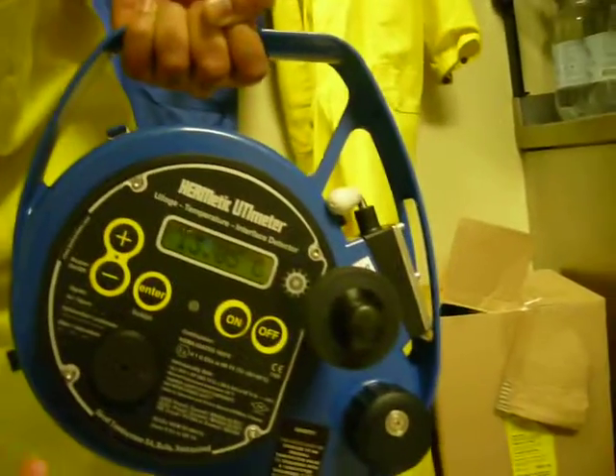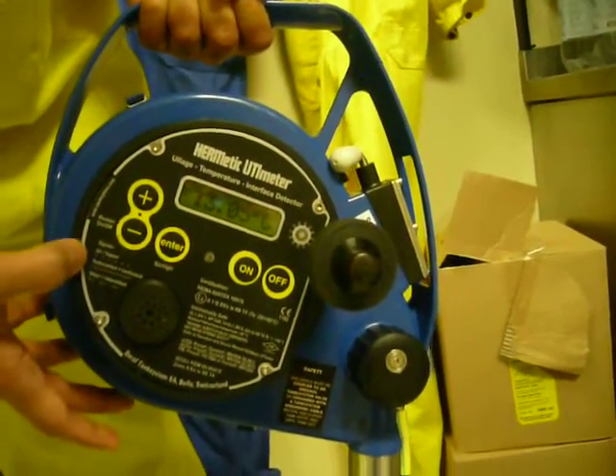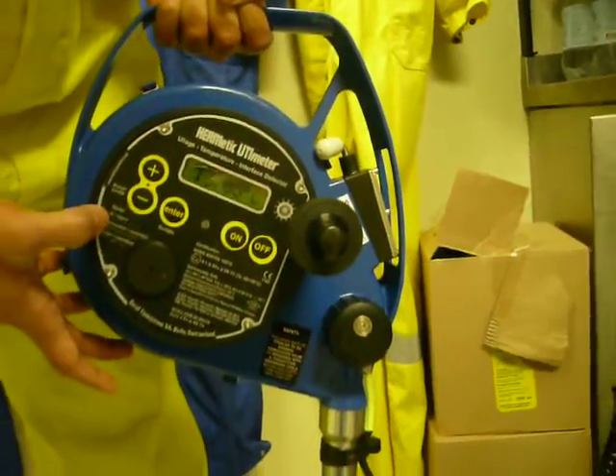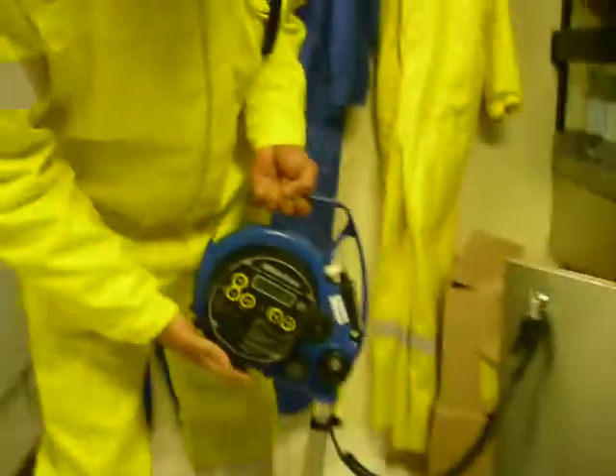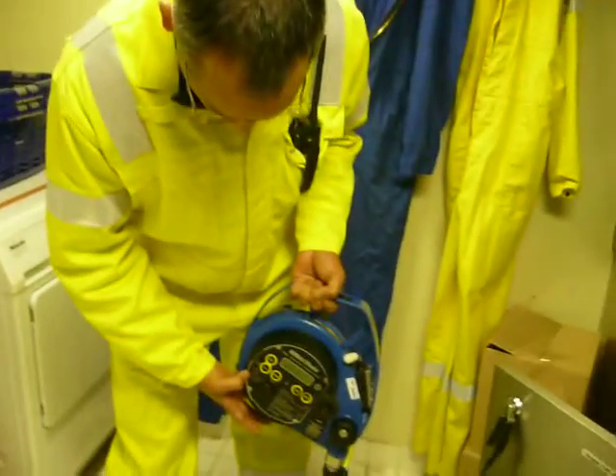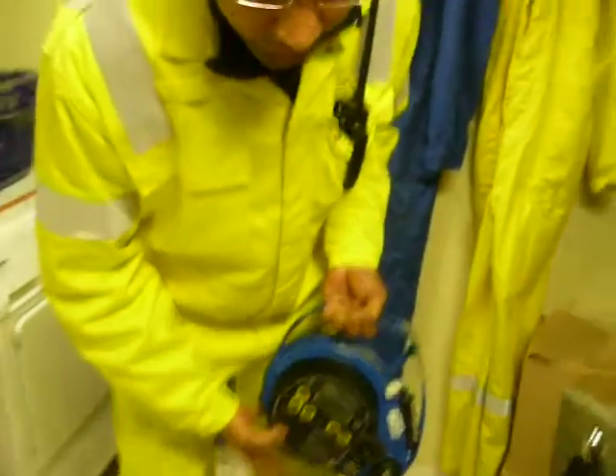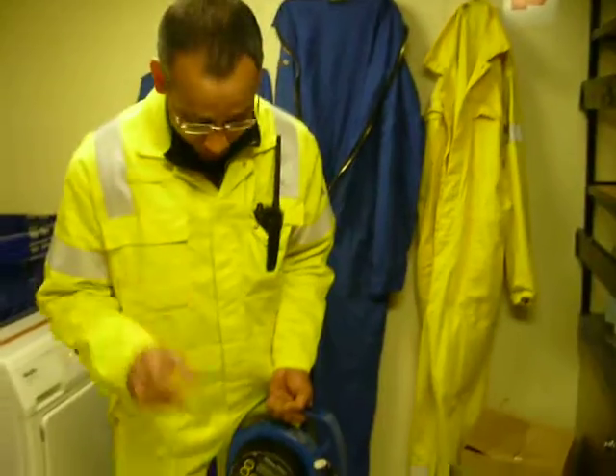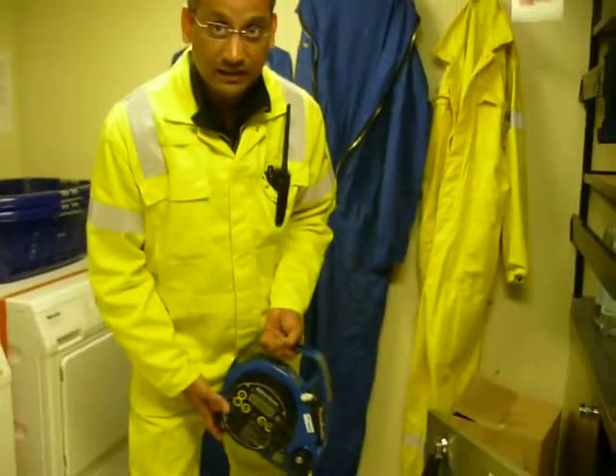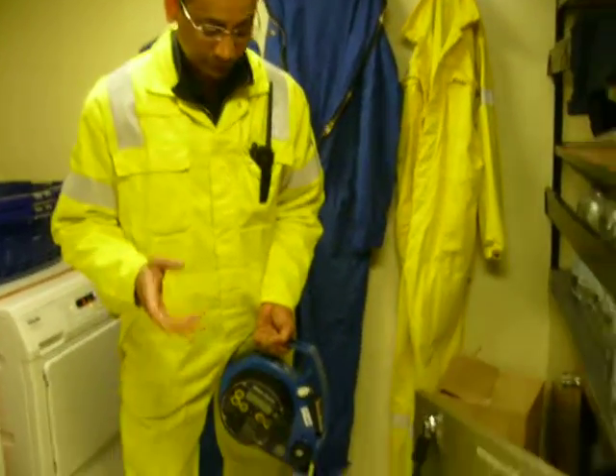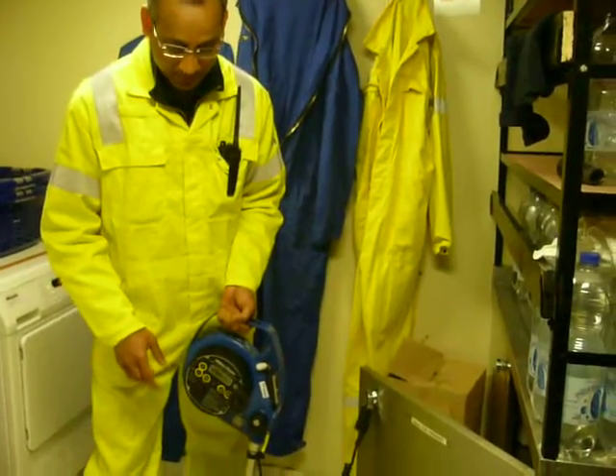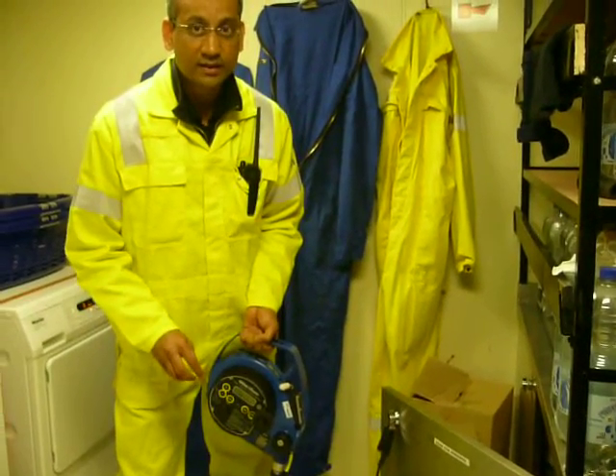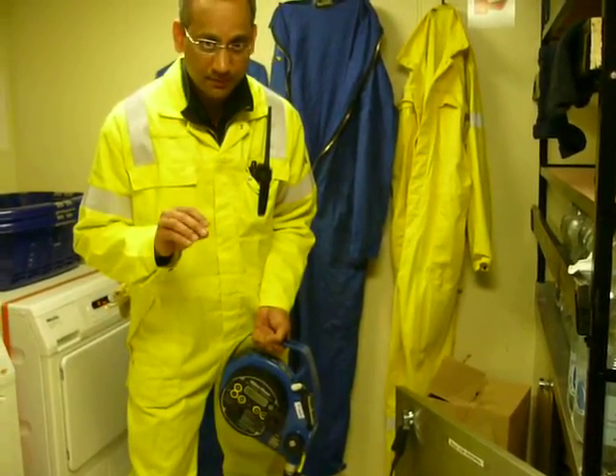If the probe of the UTI is in air or vapor, it will give you a blip, pip, pip, you can hear it. If it touches hydrocarbon, it will give a continuous blip sound. And if it detects the interface, especially the water and hydrocarbon interface, it will give an intermittent blip, pip, pip, pip, pip.